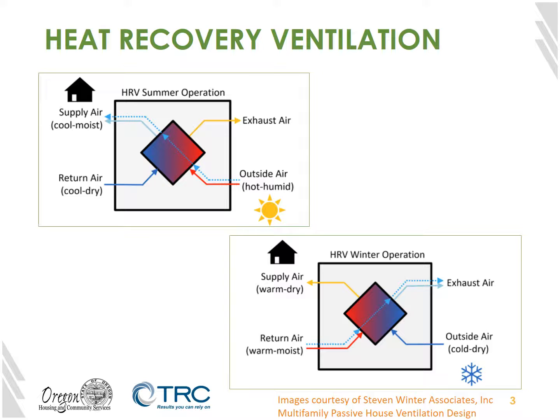Let's start talking about heat recovery ventilation and the pros and cons of its use during different times of the year. An HRV in summer introduces outdoor air with all the potential moisture and higher temperatures that come along with it. The higher efficiency models will transfer incoming heat better to the exhaust air, ensuring that the unit is not operating as a heater during the summertime.